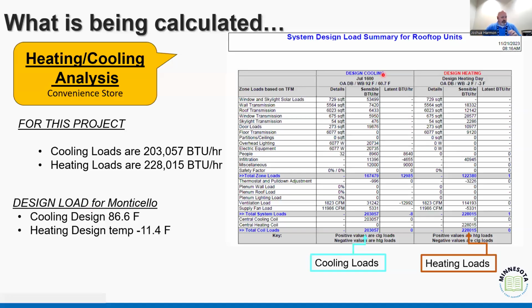So the goal in the calculation is that if I'm going to cool at about 4 o'clock in the afternoon on a July day, which is the peak temperature according to the smart people that track heating and cooling temperatures across the country, across the world. ASHRAE has a website that you can go to and plug in. The code tells us we're using the 2013 data.